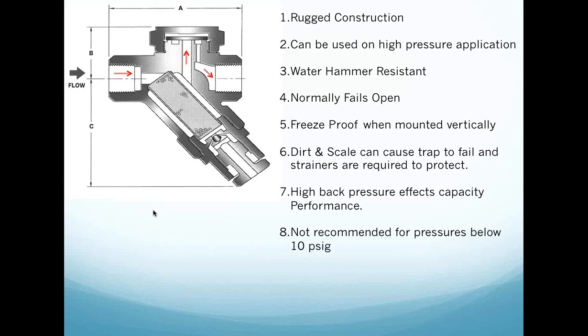A high back pressure affects the performance capacity. The traps are not recommended for low pressures below 10 pounds. So this is not a trap that you would use in a lower pressure application. But remember, there is no one perfect trap yet that I have seen, and that's one of the reasons why in those particular low pressure applications we would look at a different technology.